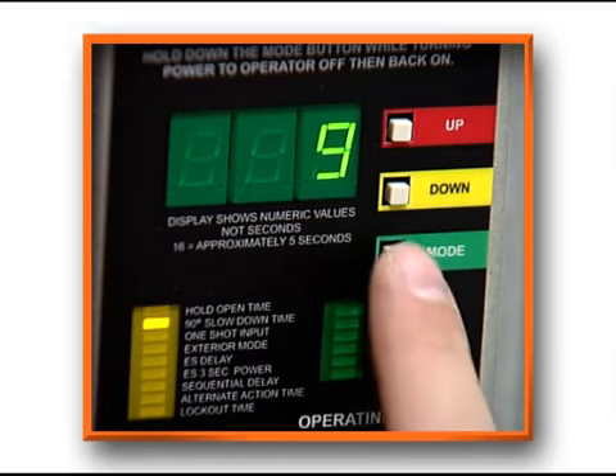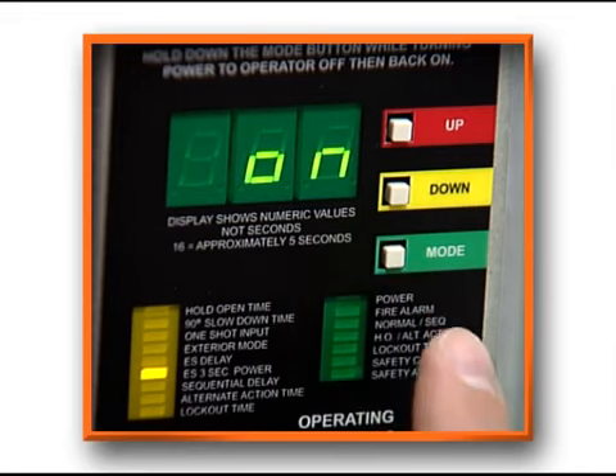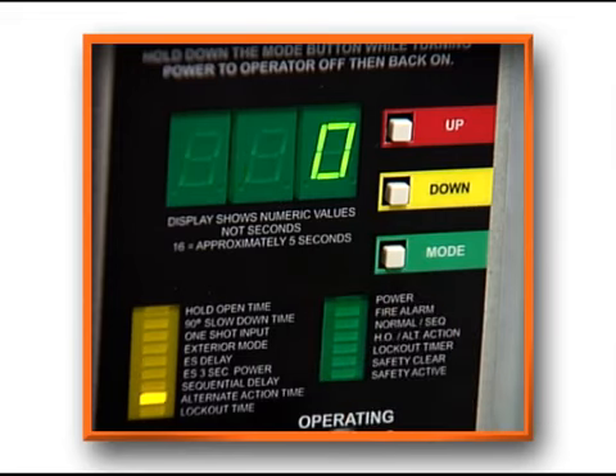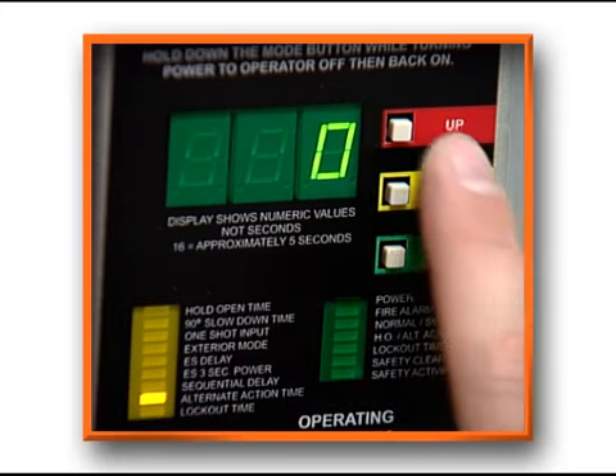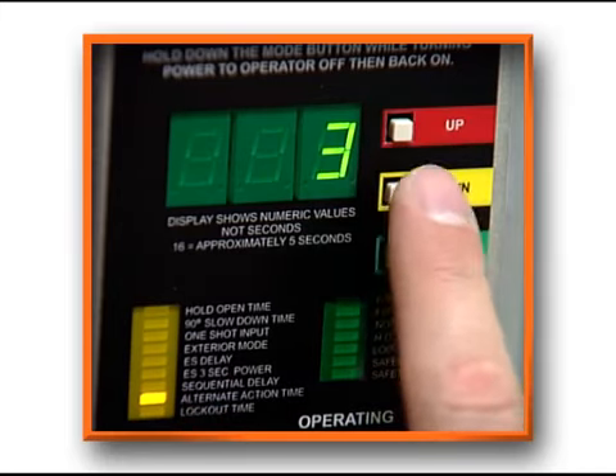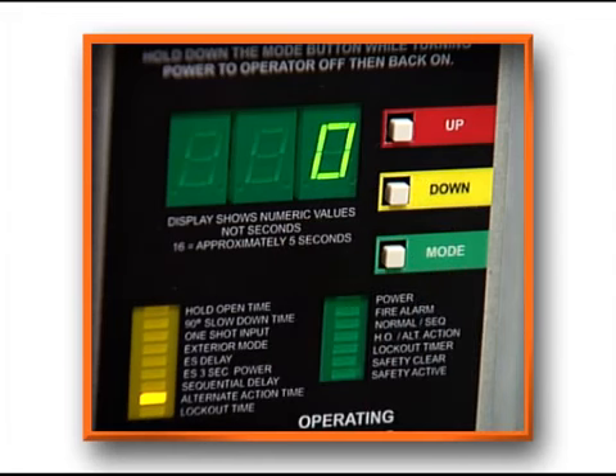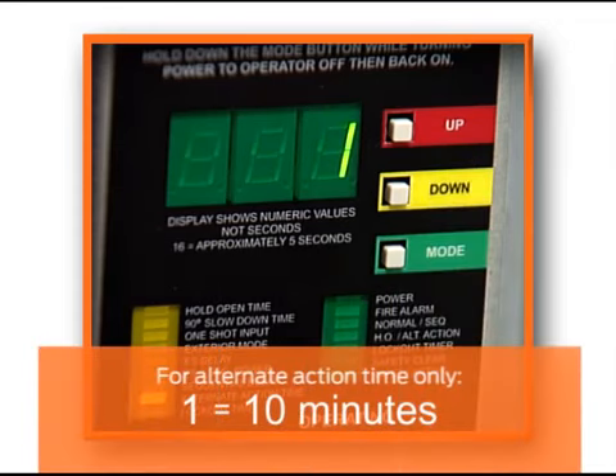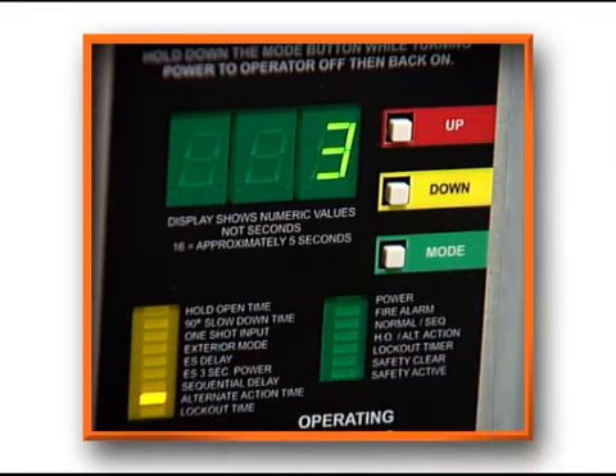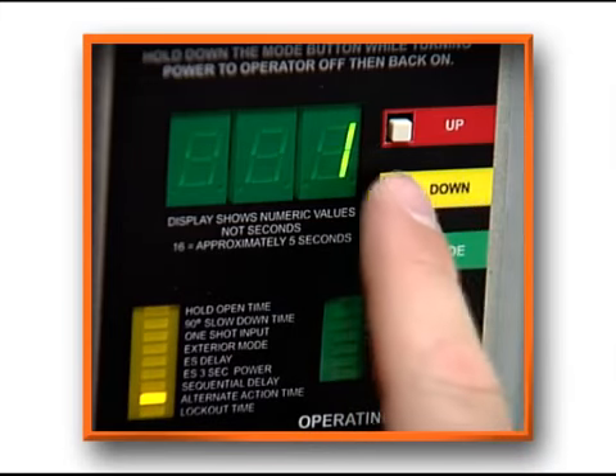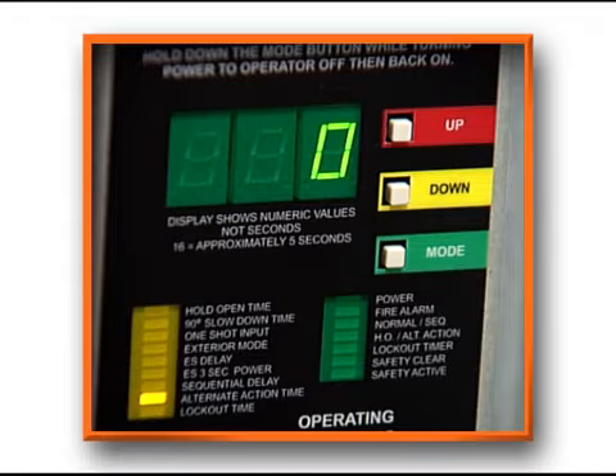The alternate action time controls the time the door will remain open after an alternate action input is received. An automatic second input to close the door kicks in if a second alternate action input is not received within the preset time. You can set this to 0, 1, 2, or 3. The default is 0, which means the door remains in indefinite hold open position until it receives a second input. 1 equals a 10-minute hold open time, 2 equals a 20-minute hold open time, and 3 equals a 30-minute hold open time. During any of these hold open times, if the operator receives a second input, the door will close.